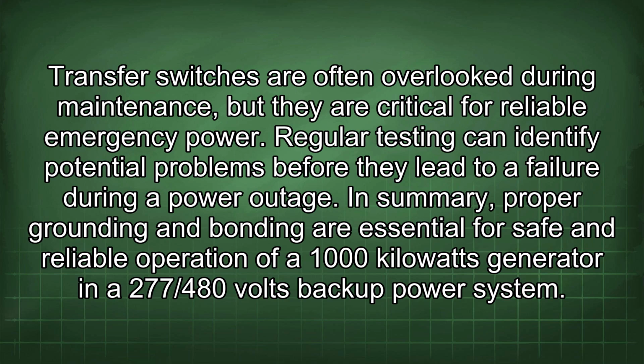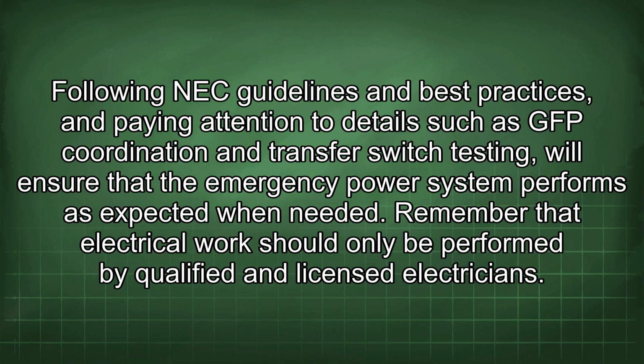In summary, proper grounding and bonding are essential for safe and reliable operation of a 1000 kilowatts generator in a 277/480 volts backup power system. Following NEC guidelines and best practices, and paying attention to details such as GFP coordination and transfer switch testing will ensure that the emergency power system performs as expected when needed. Remember that electrical work should only be performed by qualified and licensed electricians.